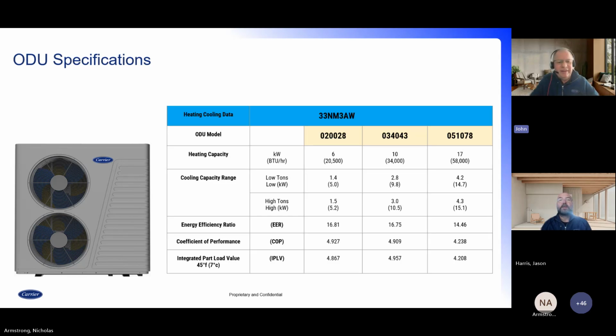Okay. So some of the efficiencies of this product: the COPs are 4.9 on the small sizes and 4.2 on the large size. We're using an integrated part load value as an average. We take the 25, 50, 75, and 100% operation, and we use that as an integrated part load value. Because it's an average, you just get a single number for that. So we're at 4.8 to 4.9, and 4.2. It's very similar to the COPs. Okay, next.